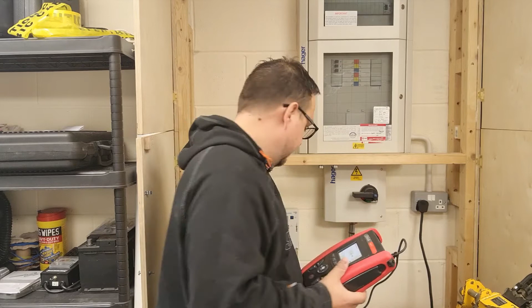There are some clamp meters for earth leakage current measurement that don't work on the earthing conductors. They only work around the phases and the neutral. This does both, so you can pop it in this instance as I've done across all 3 phases and the neutral conductor, and then just across the earthing conductor on its own, and we're measuring the same leakage current. Obviously if this was a single phase and you were measuring with the line conductor and neutral, you'd put both of those through the clamp meter and take that measurement, and then you could also go around the earthing conductor and take the measurement there as well.